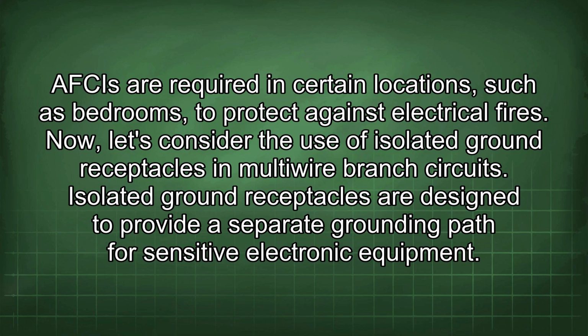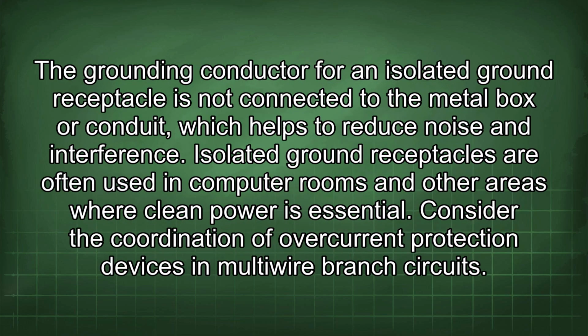Now let's consider the use of isolated ground receptacles in multi-wire branch circuits. Isolated ground receptacles are designed to provide a separate grounding path for sensitive electronic equipment. The grounding conductor for an isolated ground receptacle is not connected to the metal box or conduit, which helps to reduce noise and interference. Isolated ground receptacles are often used in computer rooms and other areas where clean power is essential.